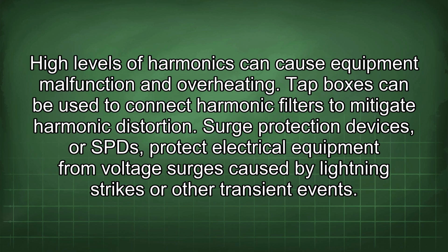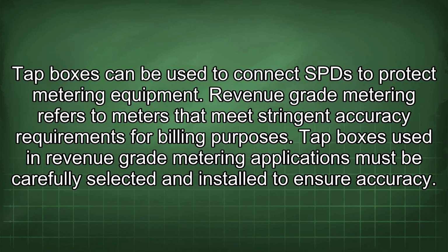Surge protection devices, or SPDs, protect electrical equipment from voltage surges caused by lightning strikes or other transient events. Tap boxes can be used to connect SPDs to protect metering equipment. Revenue-grade metering refers to meters that meet stringent accuracy requirements for billing purposes. Tap boxes used in revenue-grade metering applications must be carefully selected and installed to ensure accuracy.